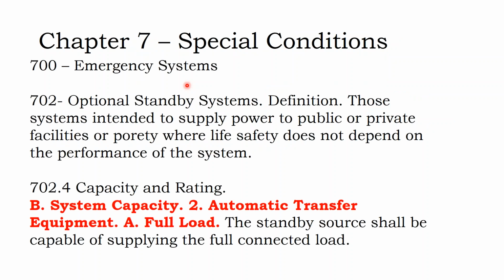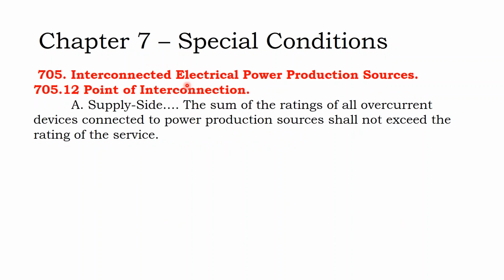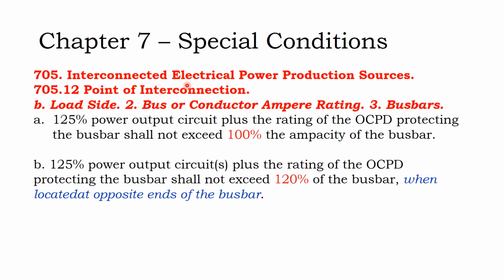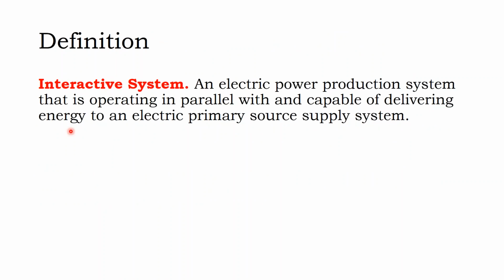So then we get beyond section 690, it's called special conditions. Your special conditions are emergency systems, standby systems, and this is also where they're putting in the microgrid aspects of multiple on-site distribution systems. And this is where that 120% rule for load side interconnections is located. That's 705.12(D) or (B). Maybe they've changed it around in this one, but that 120% rule is a special condition when you have both service power and on-site power. And so we see it appear in section 700.